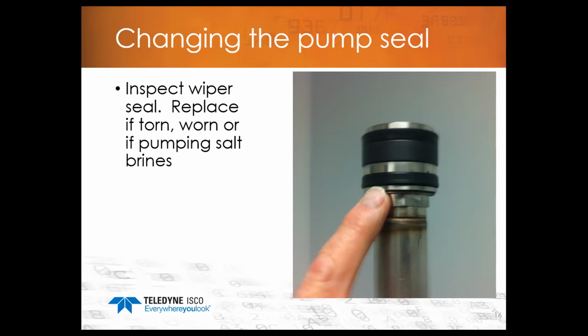And the one thing that you'll notice that's different about the wiper seal, the spring side faces downwards. So when you're looking at your piston assembly, the piston seal on top, spring side is facing up, and on your wiper seal, the spring side faces down. The only time where that will be different is on our 1000D pump.